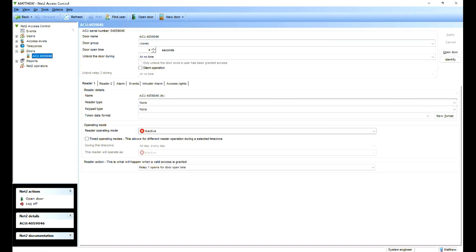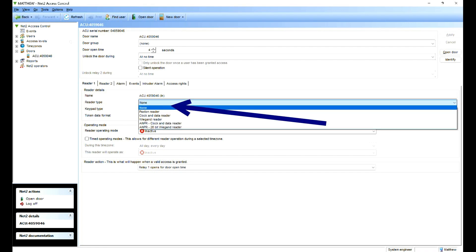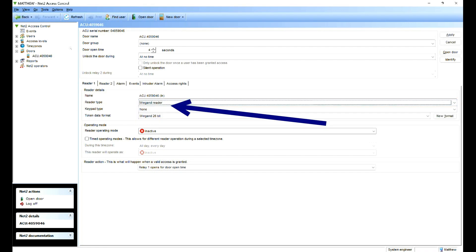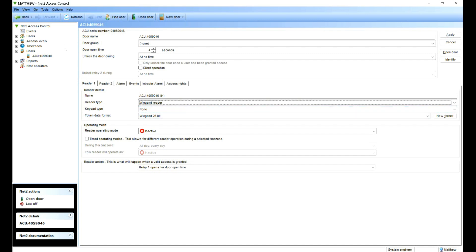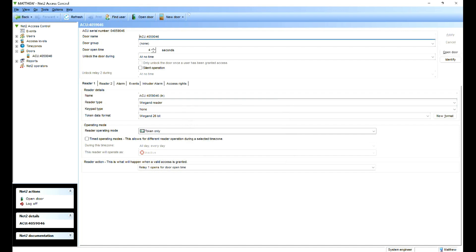And all we need to do is change the reader type. At the moment it's none. So let's change that to Wiegand. The keypad type is not used. It's 26 bit. The operating mode is inactive here, so let's change that from inactive to token only. Once we've made that change at the top there, click apply. And that's the controller now configured.